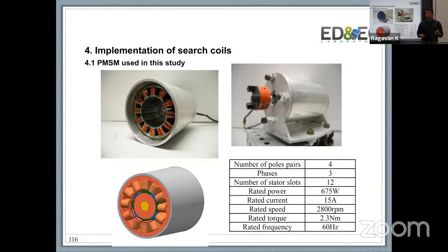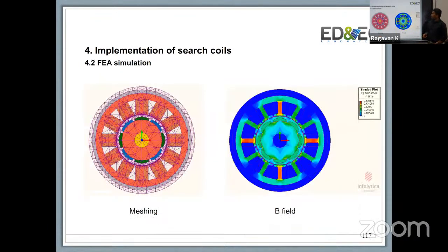And the second thing was we wanted to make sure that it was a setup that was reasonably scalable. If we can identify a signature for a small machine, then identifying it for a bigger machine is typically easier. It was a 15 amp draw, so the current draw itself was quite reasonable, but it was a 12-slot motor, and that's what made it a little more distinct. So if you do FE analysis, you've seen this before.